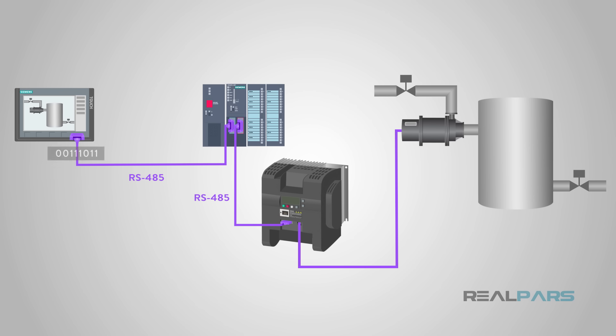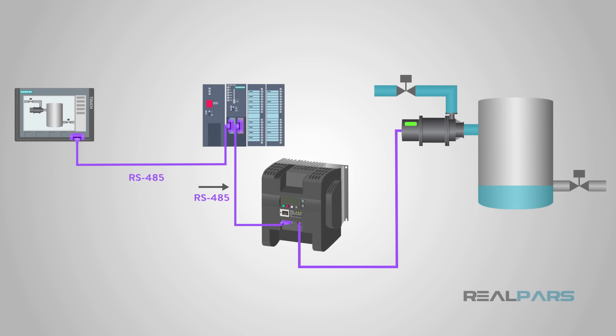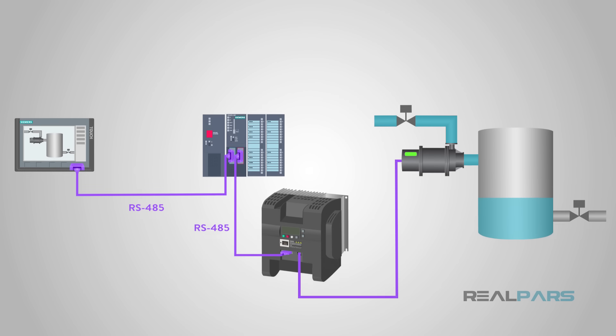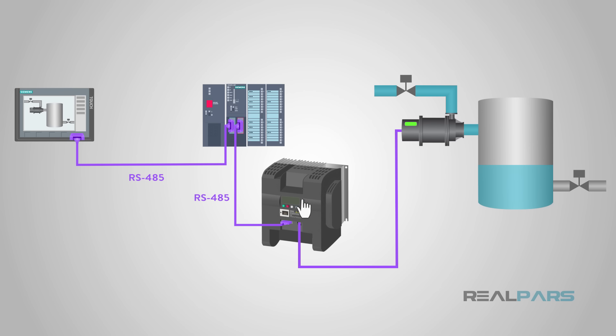Let's say you are monitoring a water pump filling a vessel, and you decide that the water is not filling fast enough to keep up with demand. With your RS-485 network, you can remotely monitor and control that pump from a control center. The HMI is connected to your PLC via RS-485, and the PLC is also connected to the VFD via RS-485. The PLC is programmed to monitor the water level in the vessel and allows manual flow control if needed. All of this allows you to speed up the VFD that controls the speed of the water pump — problem solved, thanks to RS-485 communications.